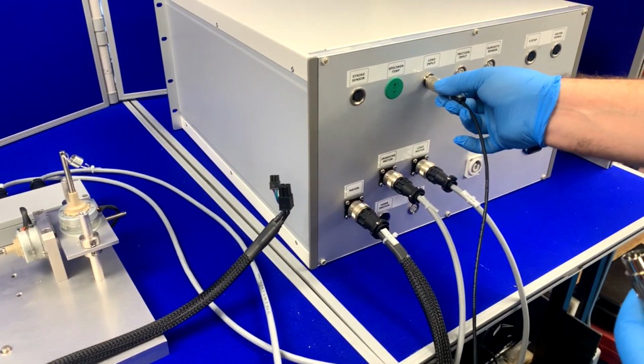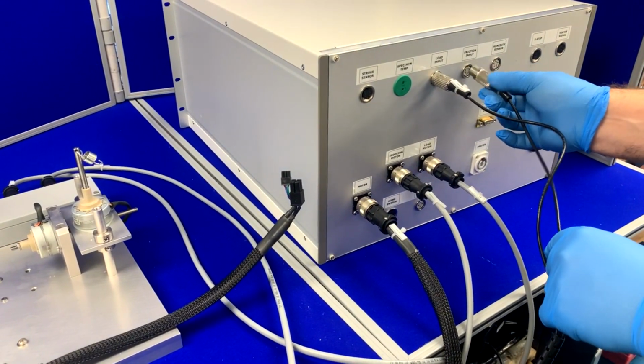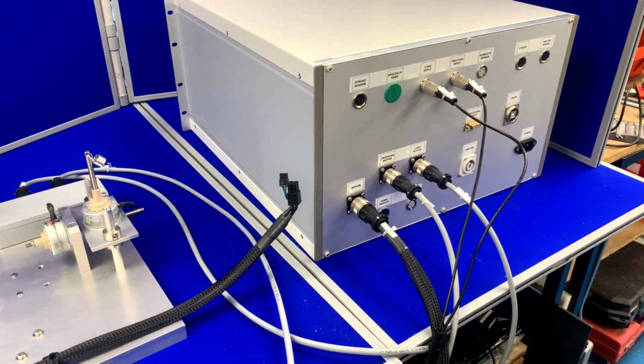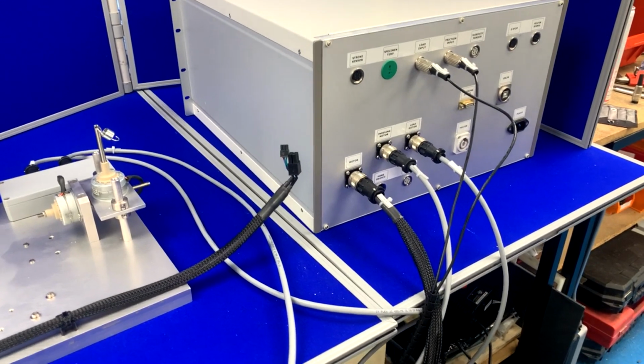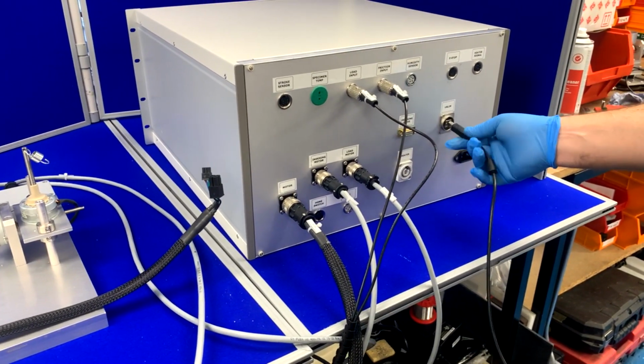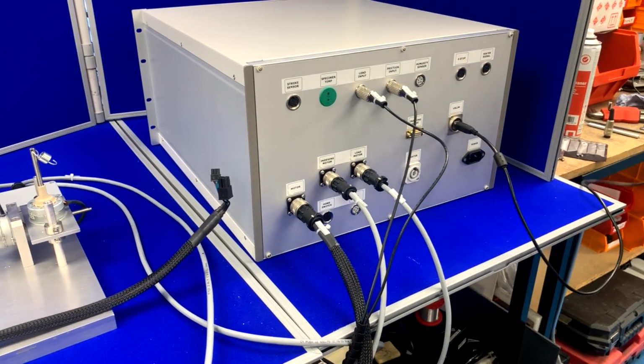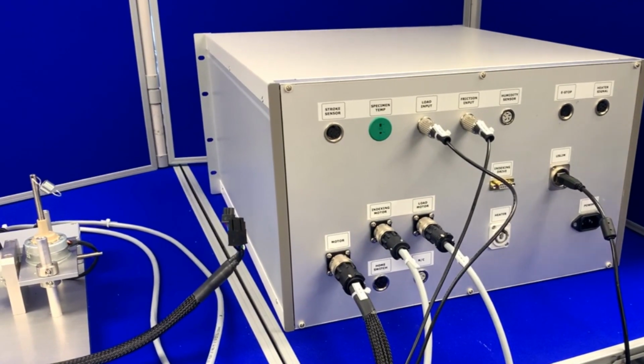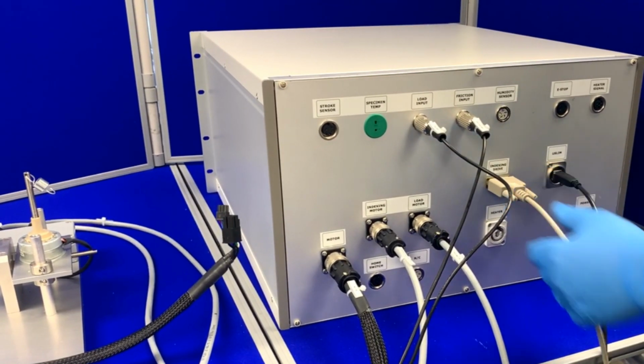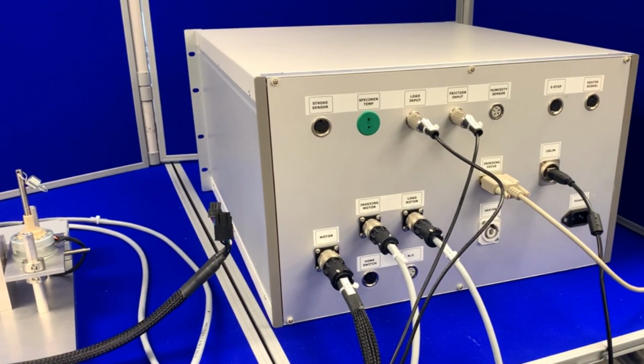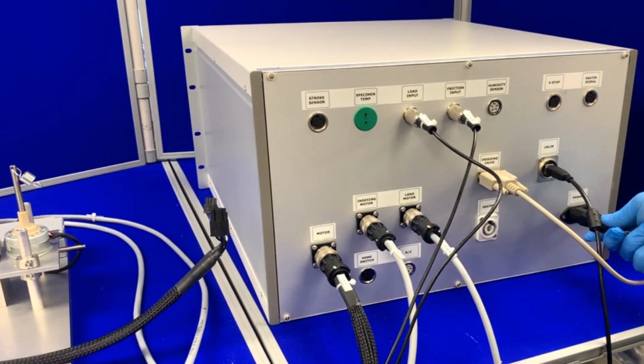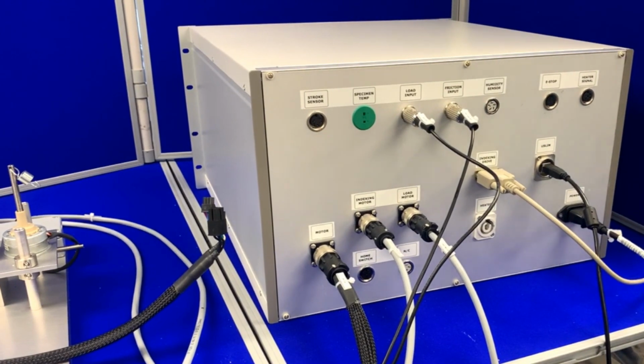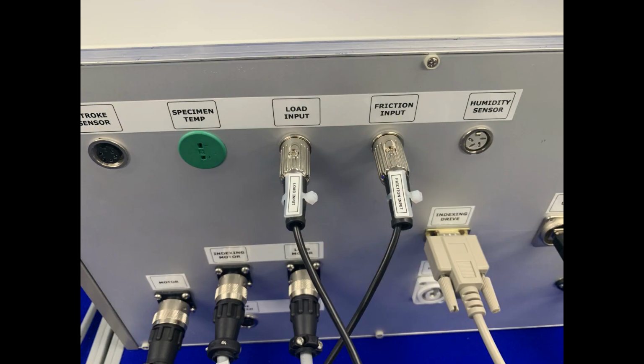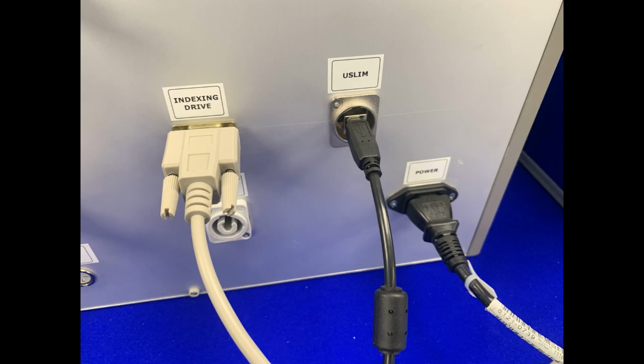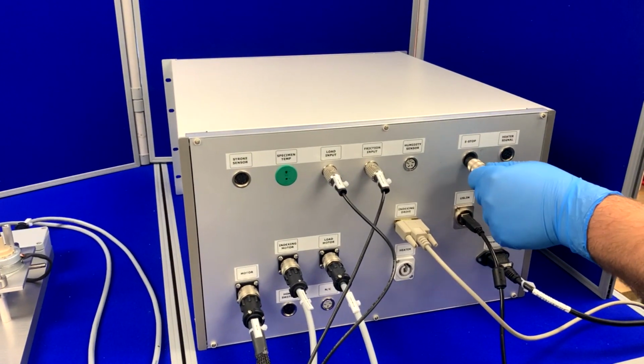Connect the load and friction transducers to the designated inputs on the cabinet. Connect the USB cable between the U-Slim socket on the back of the cabinet and the USB U-Slim port on the PC. Connect the indexing motor drive using the 9-way D connector on the back of the cabinet and the RS485 connection on the PC. Connect the power cable to the IEC socket on the cabinet. Plug in the emergency stop cable.